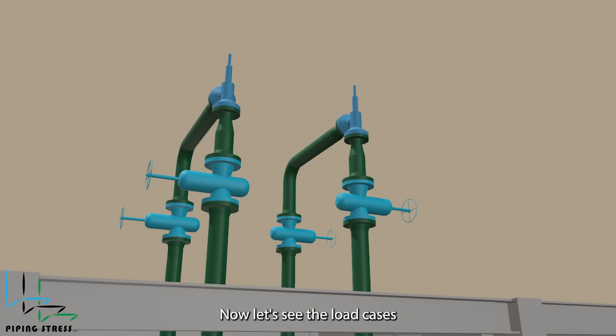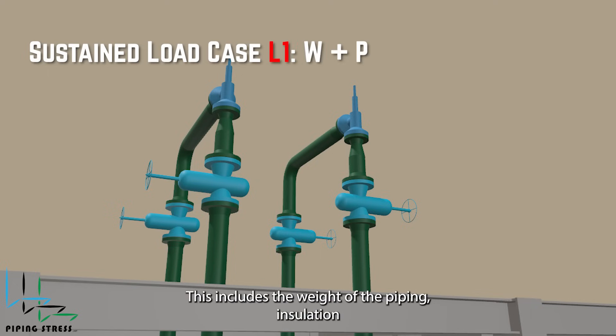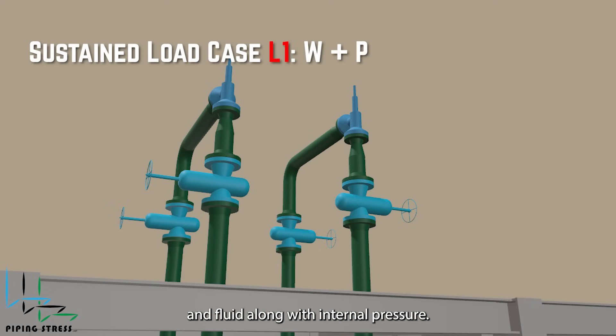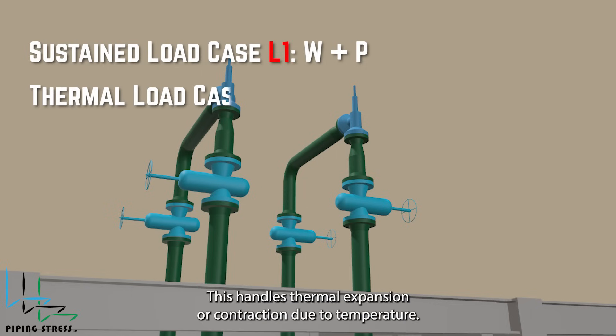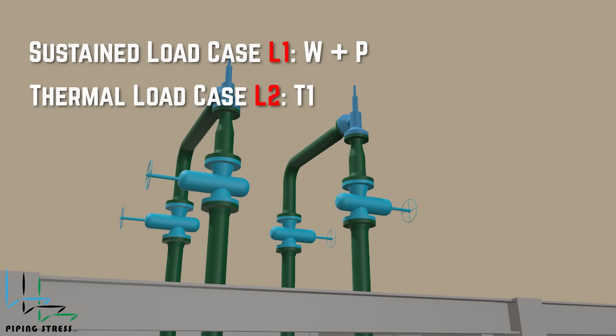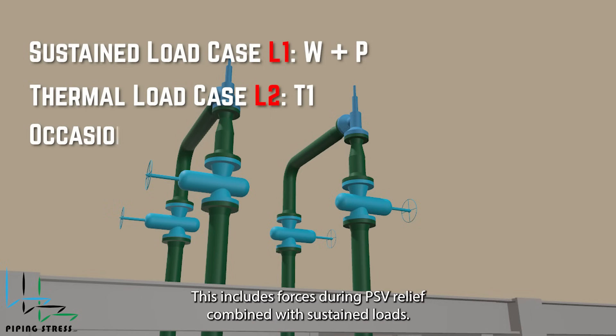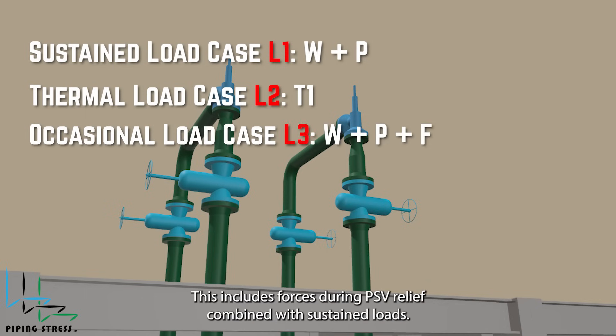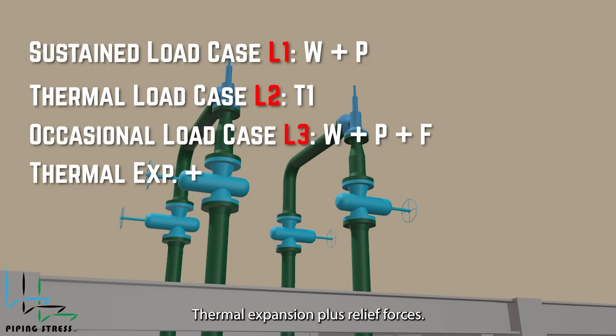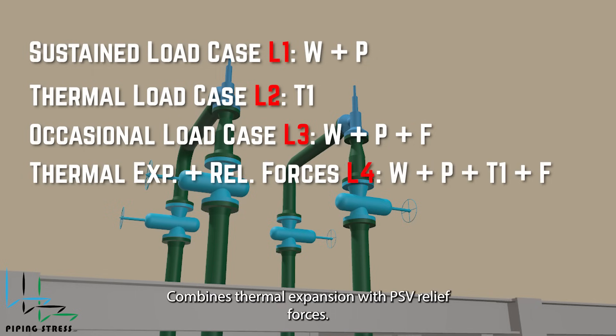Now let's see the load cases for PSVs. Sustained load case: this includes the weight of the piping, insulation, and fluid, along with internal pressure. Thermal load case: this handles thermal expansion or contraction due to temperature. Occasional load case: this includes forces during PSV relief combined with sustained loads. Thermal expansion plus relief forces: combines thermal expansion with PSV relief forces.